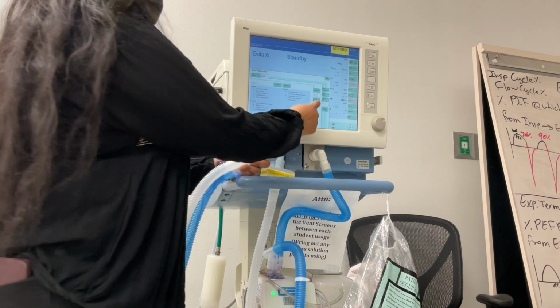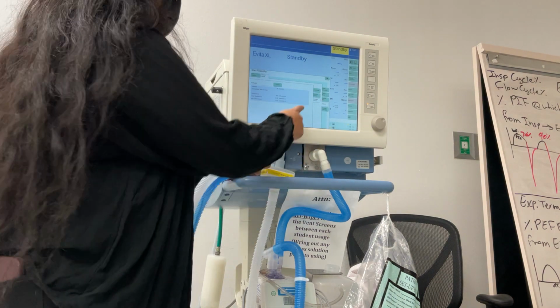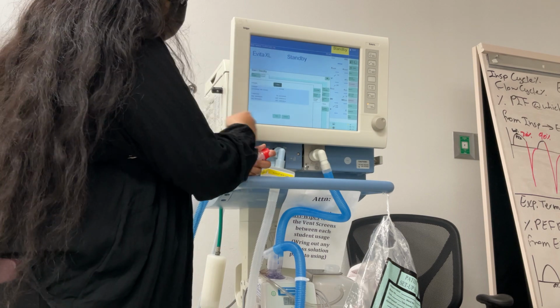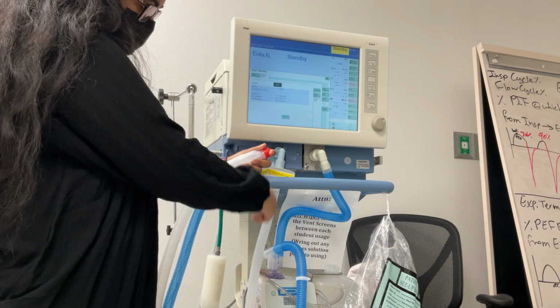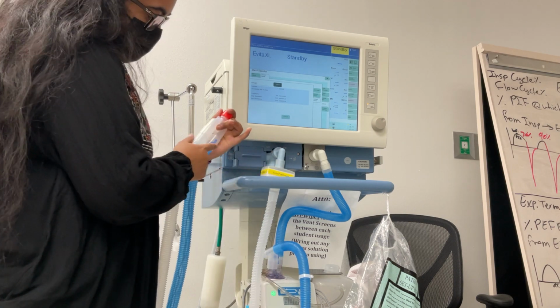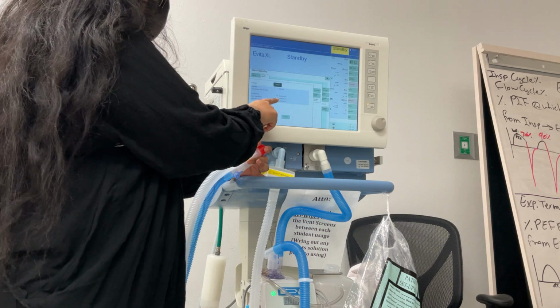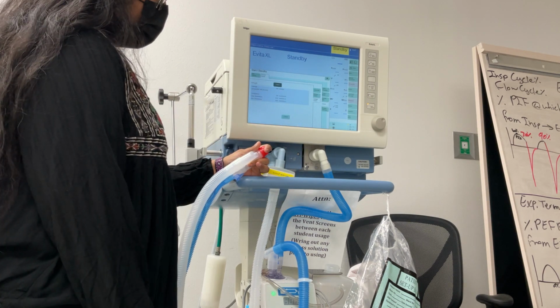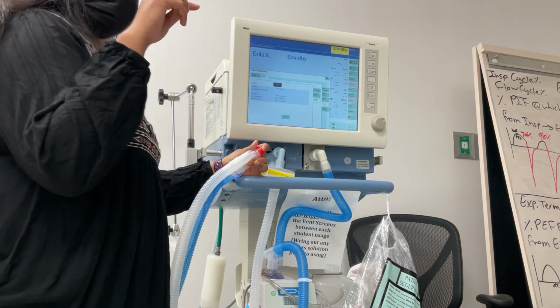So now, since you've passed through this one, you're going to go through airtight check. And then after you click that, you're going to hit check up here. It's going to tell you seal the Y piece, confirm with yes. And now it's going to look for any leaks within your circuit. If it finds a leak either here or any on the temp probes, it'll fail. It'll tell you the leakage number here, and then it won't pass. I think it'll show you a little red circle instead of a green circle.